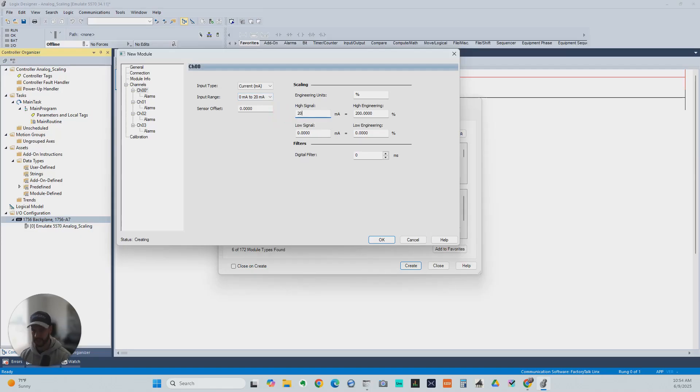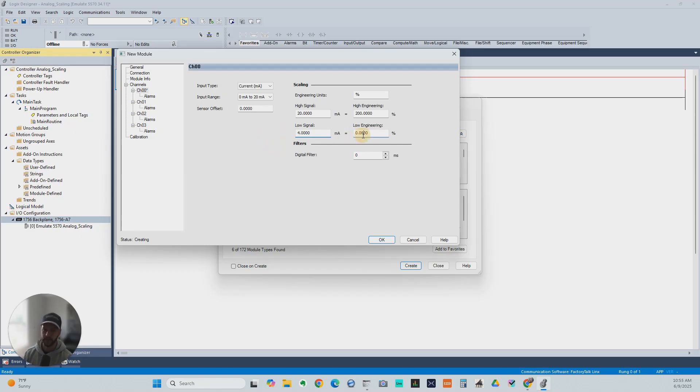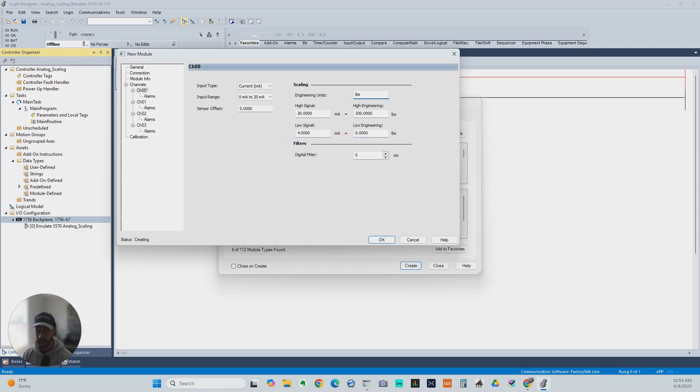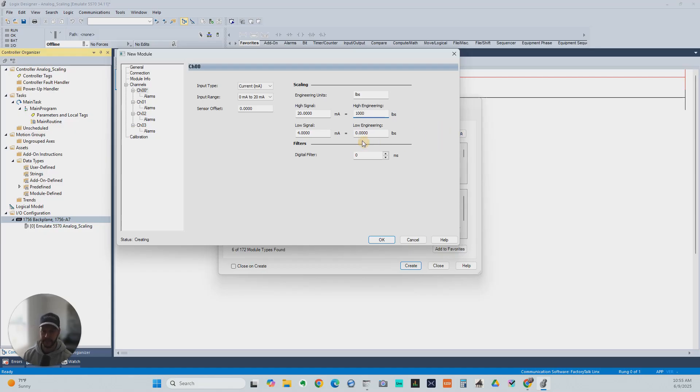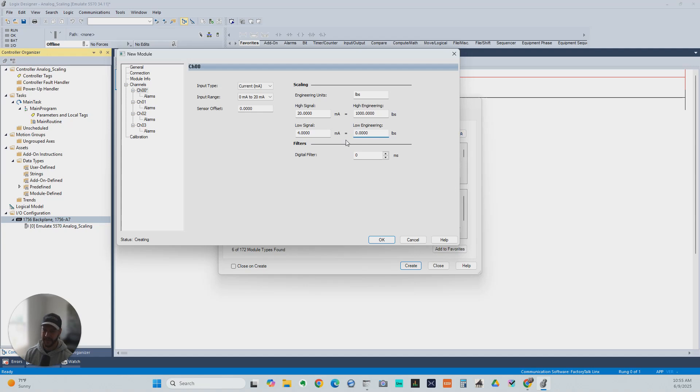Our high signal is going to be 20. Our low signal is going to be 4. We're saying that this is going to be pounds. So this is going to be 1,000 pounds. And this is going to be 0 pounds. This makes it so easy to scale this. We don't even have to do any math in our head.